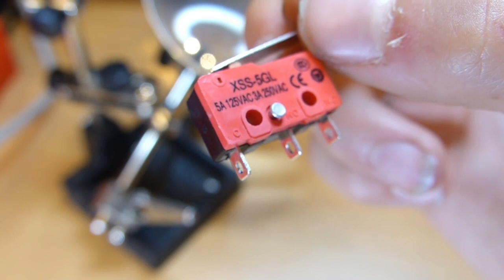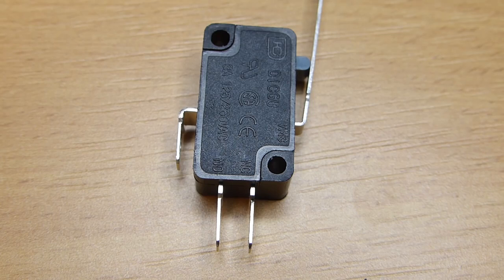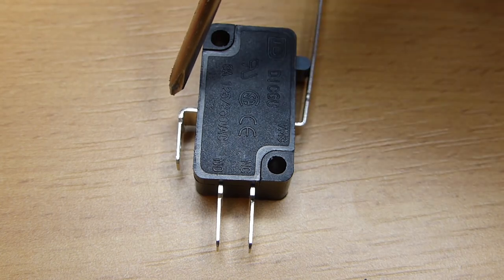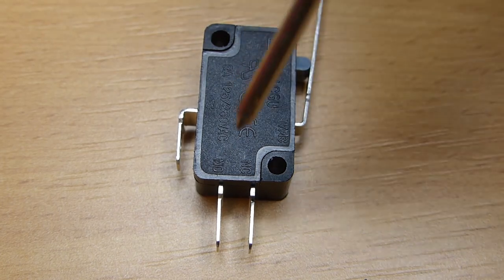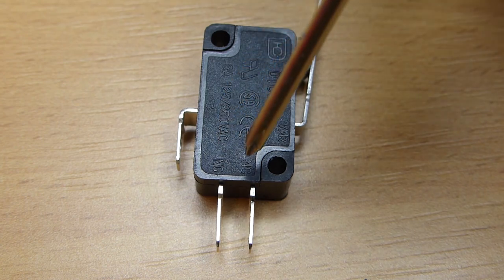One should say C or COM which stands for common, one should say NO for normally open, and one should say NC for normally closed. On these micro-switches, the side tab is always the common, and the normally open and normally closed are at the bottom.